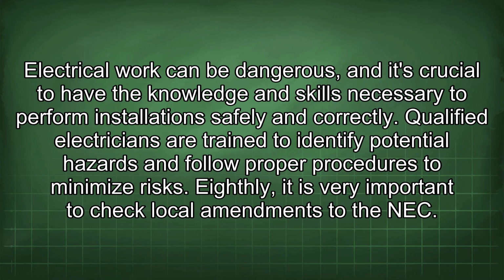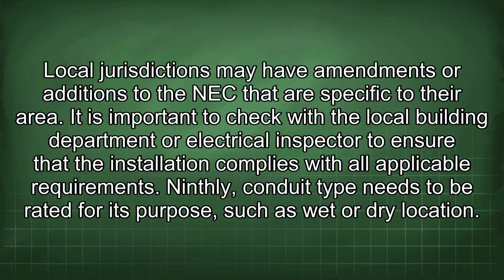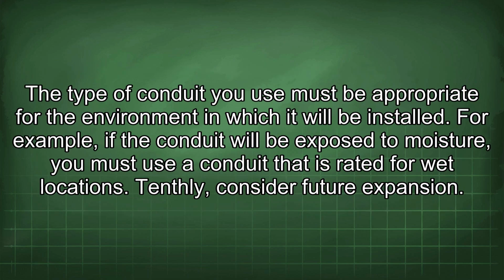Eighthly, it is very important to check local amendments to the NEC. Local jurisdictions may have amendments or additions to the NEC that are specific to their area. It is important to check with the local building department or electrical inspector to ensure that the installation complies with all applicable requirements. Ninthly, conduit type needs to be rated for its purpose, such as wet or dry location. The type of conduit you use must be appropriate for the environment in which it will be installed. For example, if the conduit will be exposed to moisture, you must use a conduit that is rated for wet locations.